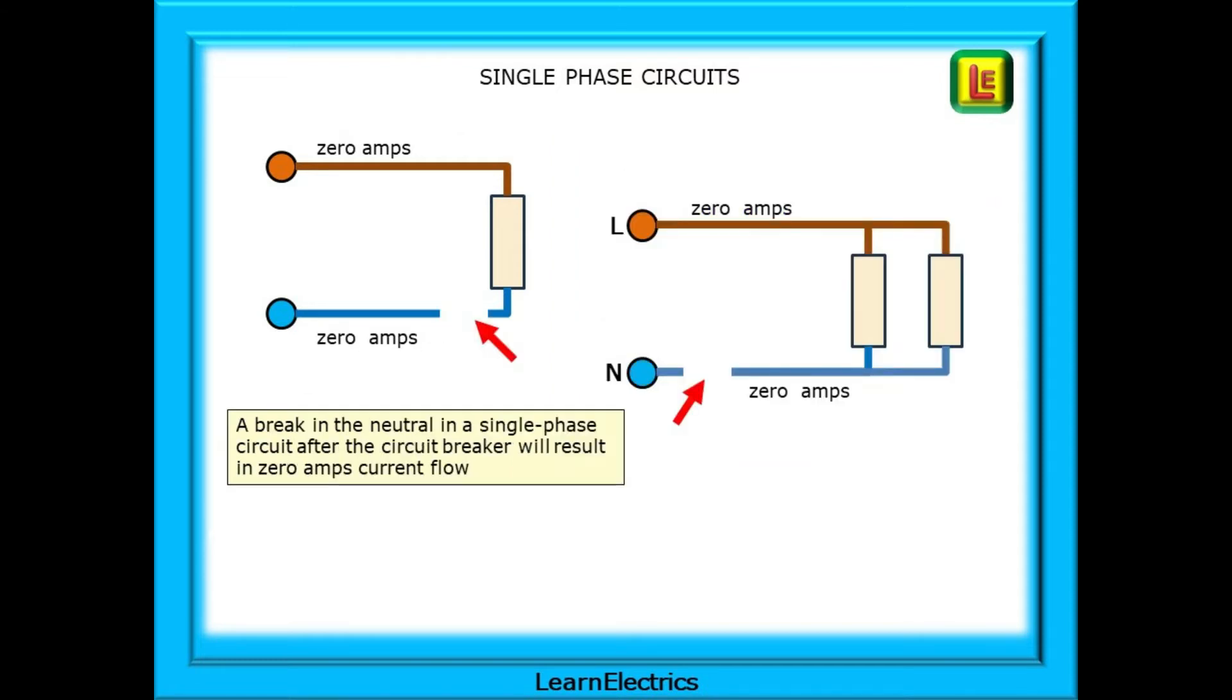When we talk about single-phase circuits losing a neutral, we're looking at problems in the final circuit part of an installation, the wiring after the circuit breaker. A break in the neutral in a single-phase circuit after the circuit breaker will result in zero amps current flow. If the neutral to the cooker, for example, is broken, the cooker will not work. Yes, there might still be electric at the cooker, but it will not be damaged, it just stops working.